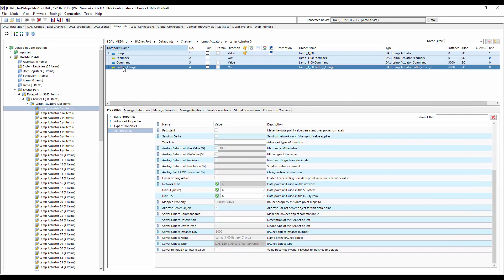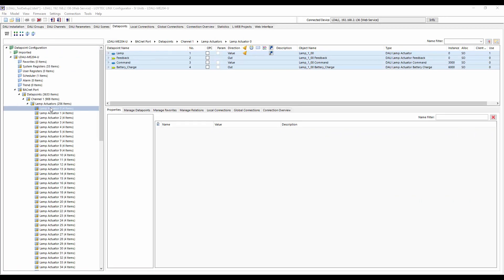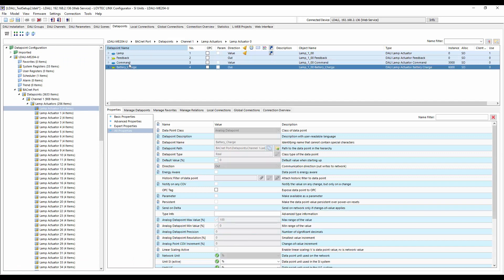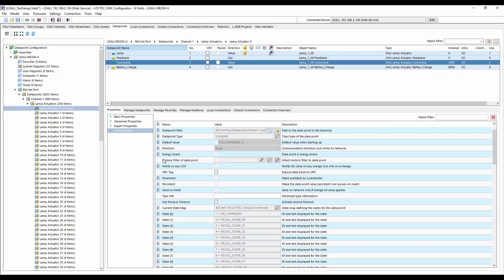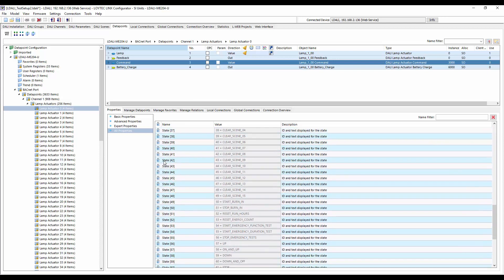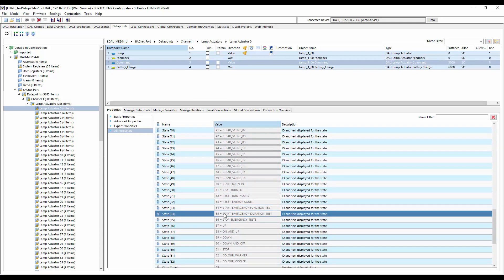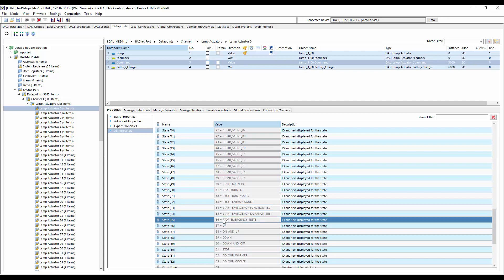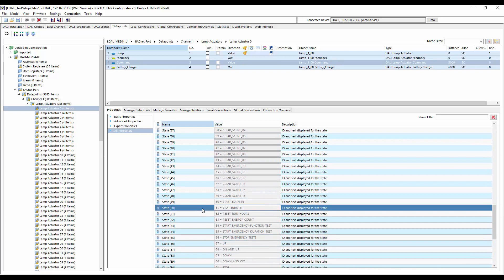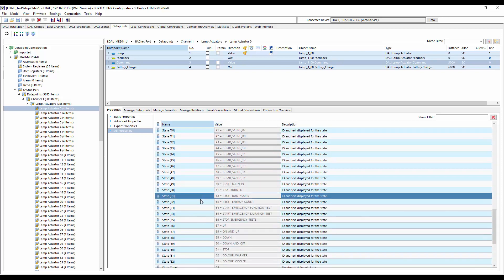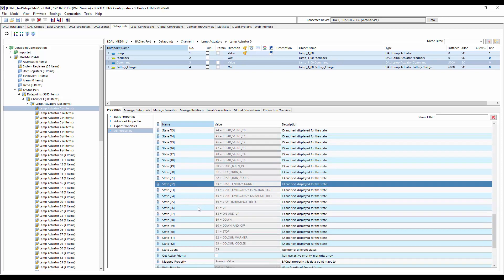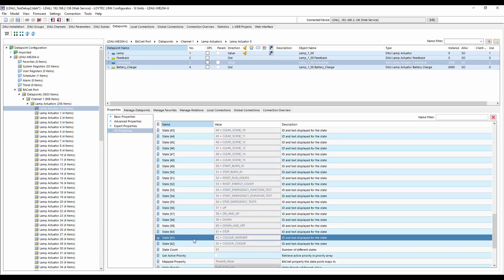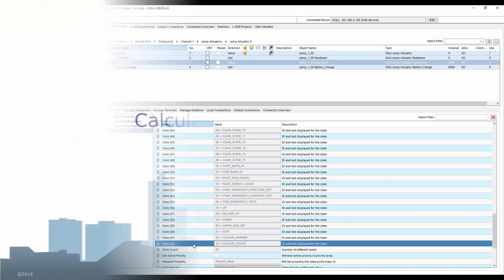Another new object is the analog input object, which allows to determine the battery status of self-contained emergency lights. Furthermore, with these two new object types, additional functionality becomes available via BACnet interface. Like starting and stopping self-test of DALI's self-contained emergency lights, reading the battery status of DALI's self-contained emergency lights, starting and stopping the burn in function, resetting run hours and energy counters, relative dimming up and down, relative changes of color temperature, warmer and cooler for DALI lamps with tunable white support.